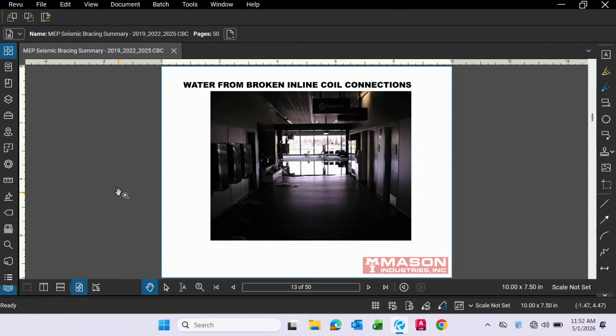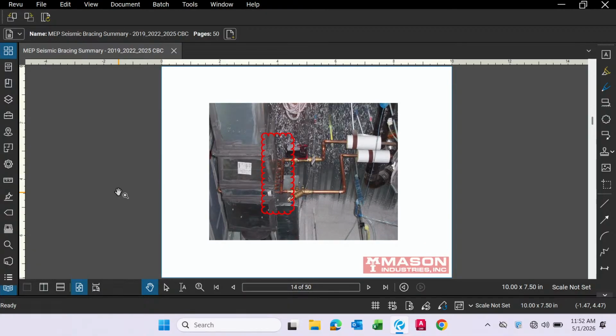In this example, I don't know if you can see it in the back, but that right there is actually water, flooding the hallway of the hospital. Patients had to be evacuated because of non-structural damage. The damage was caused when these small pipes connected to the fan coils, those soldered connections, failed because the relative displacement was not accounted for. So a lot of those fan coils leaked and caused flooding in that hospital, even though the main building stayed in place.